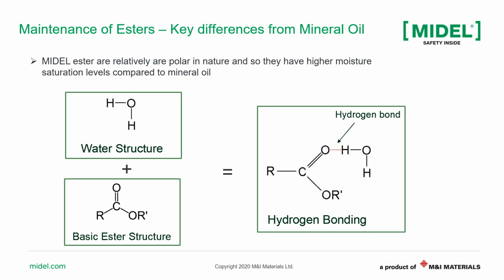For the in-service limit, one of the key parameters is the moisture tolerance. Here we justify why esters can have high moisture content without breaking down, reducing the breakdown voltage. You can see the basic ester structure really is a polar structure, so it has a slight polarity, and the water molecule is also polar. With both of them together, they can bond like a magnet in a hydrogen bond, not a permanent bond, but this allows the esters to dissolve or absorb more moisture, so they have high saturation levels. This is the fundamental explanation.